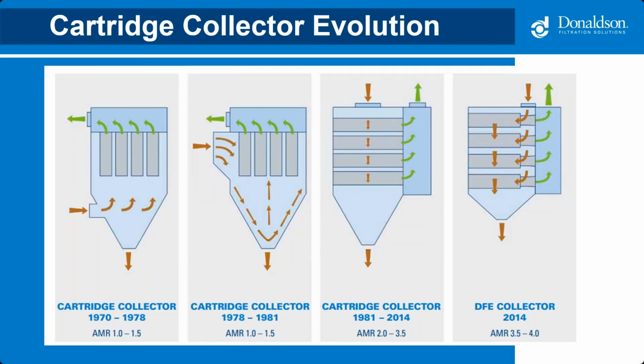This change resulted in an incoming airflow pattern aligned with the desired final location of the dust discharged from the filter cleaning. Since gravity naturally directs discharged dust particles down towards the bin or drum at the bottom of the collector, the incoming air pattern of a downflow collector could now assist with the movement of particles to the containment vessel at the base of the unit rather than fighting against it.